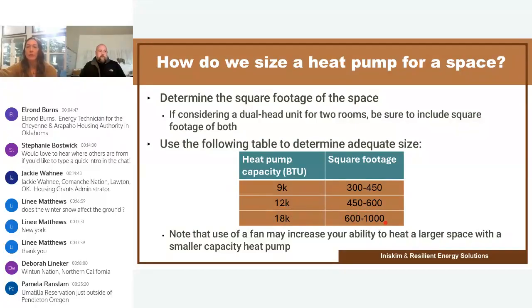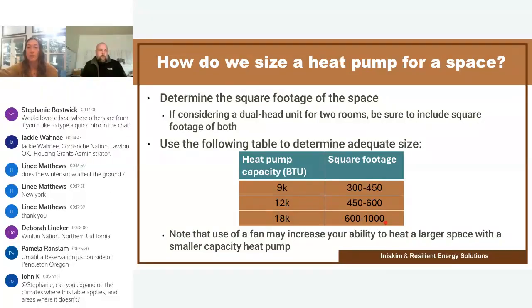But we have a note that says if you use a fan, you may increase your ability to heat a larger space. We've talked to folks who have a heat pump in a bedroom and use a box fan to blow the heat out into the rest of the home, and that works really well. Or a ceiling fan that circulates the air can be really helpful. A lot of folks retrofitting will put a head unit in the living room first, connected to the kitchen and other open areas, and using a fan to circulate that air through those areas helps.